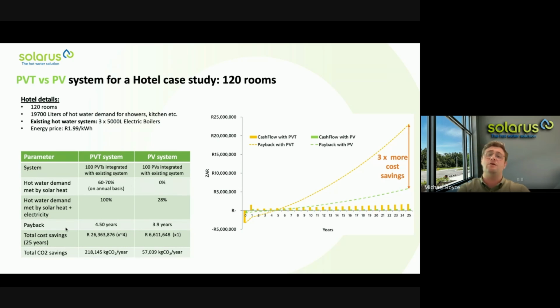This hotel has just over 200 square meters of roof space available to deploy renewables. We ran a simulation comparing both PV and PVT systems to give the client the most informative decision. We suggested both a 100 PVT system and a 100 PV system. The hot water demand met by solar heat on the PVT system is between 60 and 70% on an annual basis, while the PV system produces none of the heat required since it doesn't produce heat.